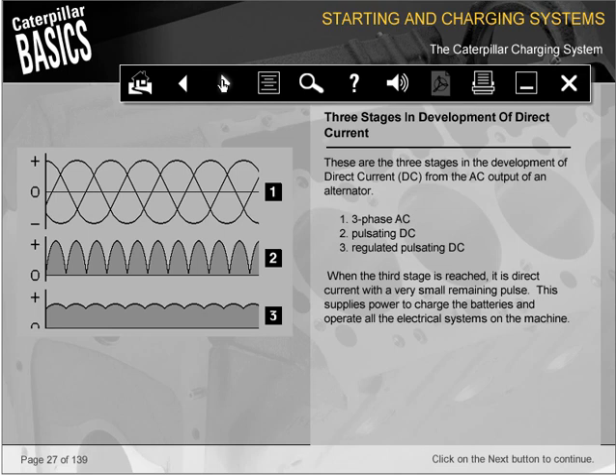These are the three stages in the development of direct current, DC, from the AC output of an alternator. 1. Three-phase AC. 2. Pulsating DC. 3. Regulated pulsating DC. When the third stage is reached, it is direct current with a very small remaining pulse. This supplies power to charge the batteries and operate all the electrical systems on the machine.